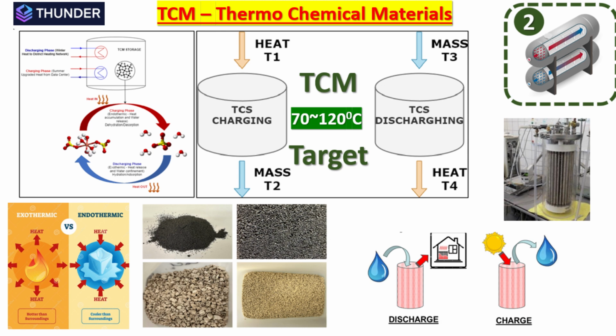But to use the salts meaningfully, you need a surface area for absorption. The most common material is vermiculite, or similar materials that absorb the salt. When moisture is introduced, it reacts and generates heat. But once the heat is generated, the material becomes saturated, and you need excess heat to dry it out and remove the water so it can be reused.